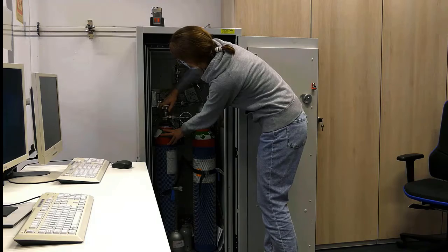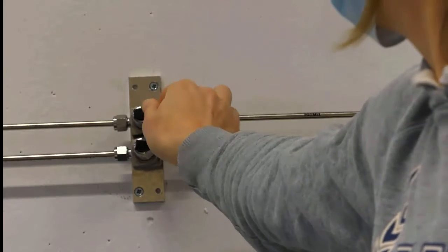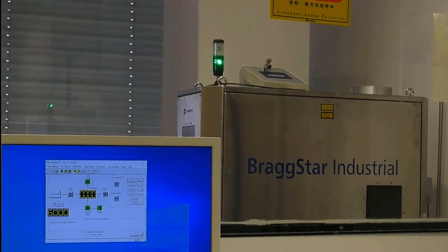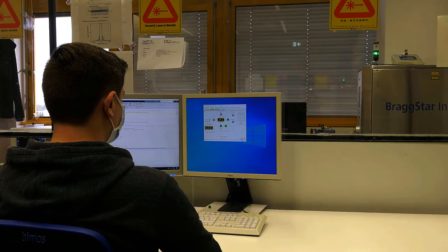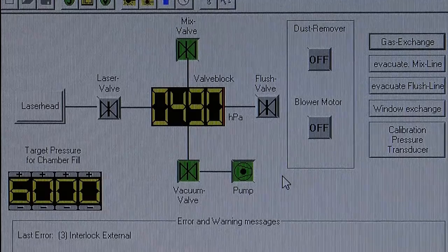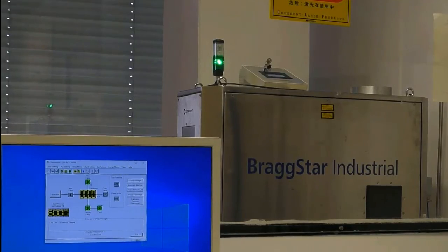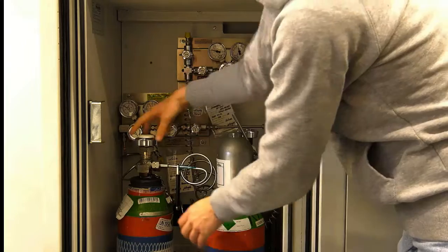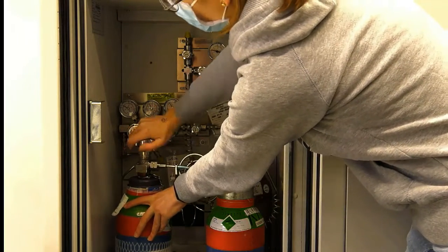Before we can start the laser, we have to do a gas exchange, because the laser gas degrades over time. Therefore, we can start the automatic gas exchange, where the old gas is removed and the laser head is filled with new gas. Once the gas exchange is done, we close the gas bottles and we can start lasing.